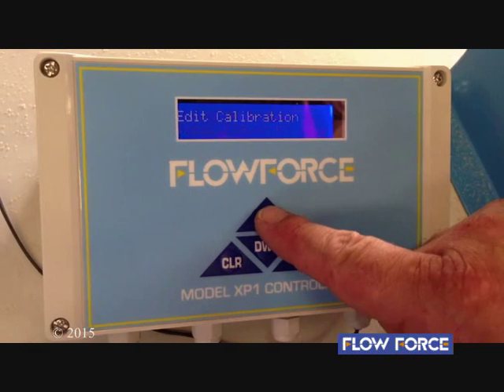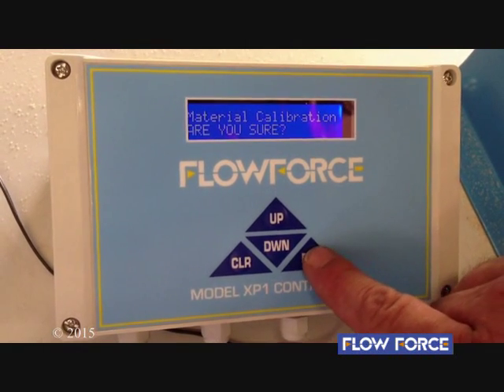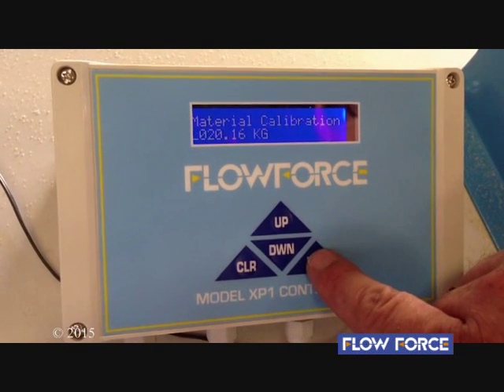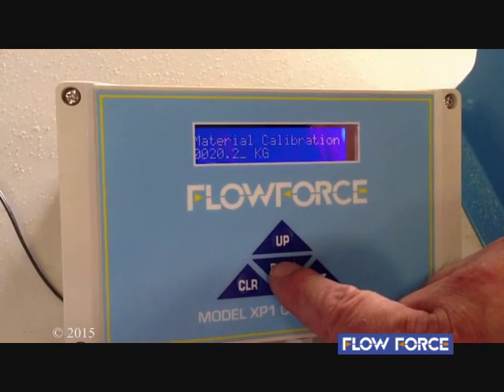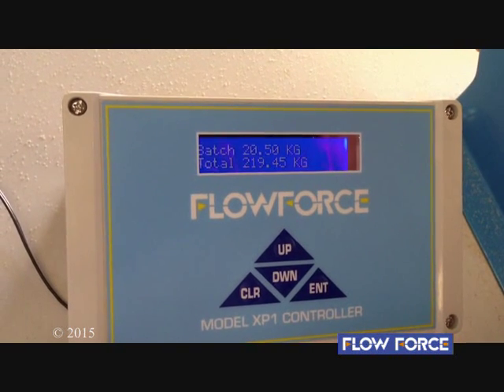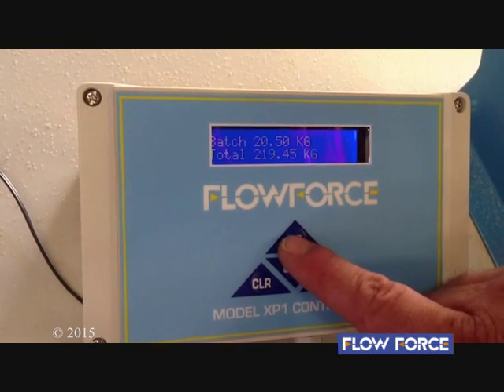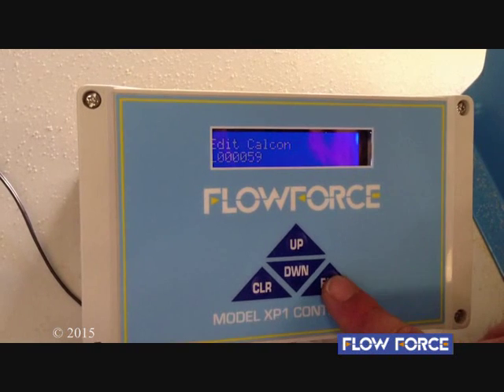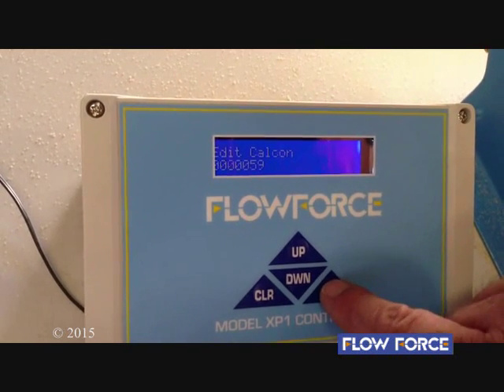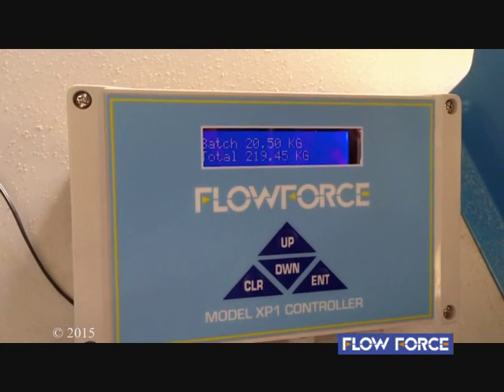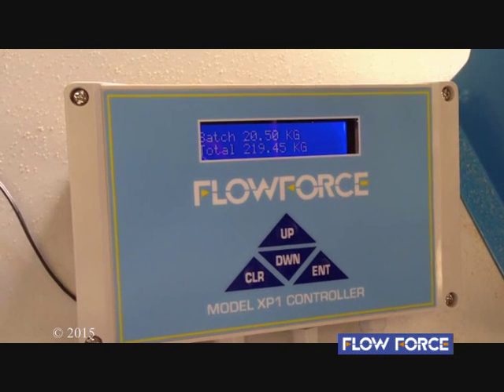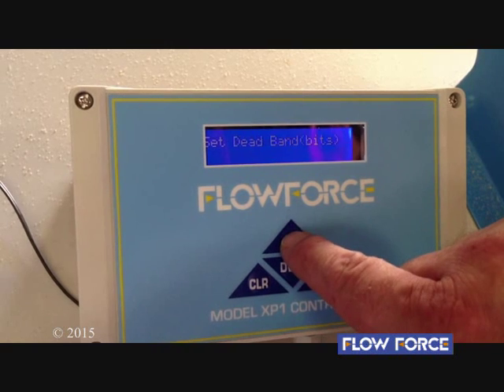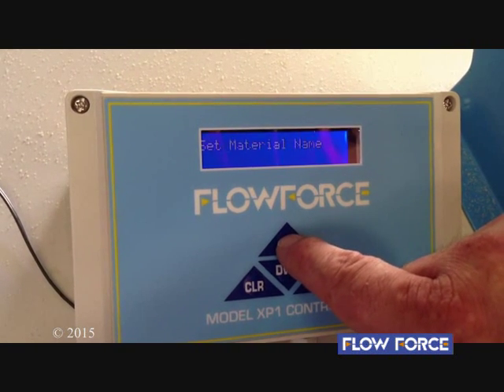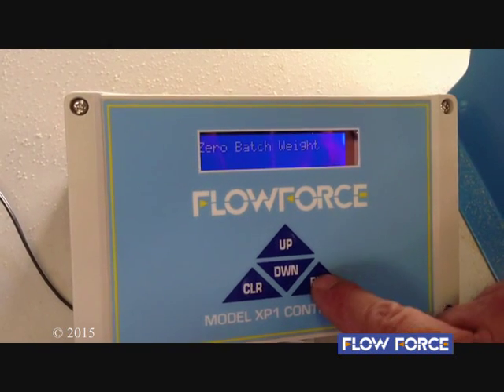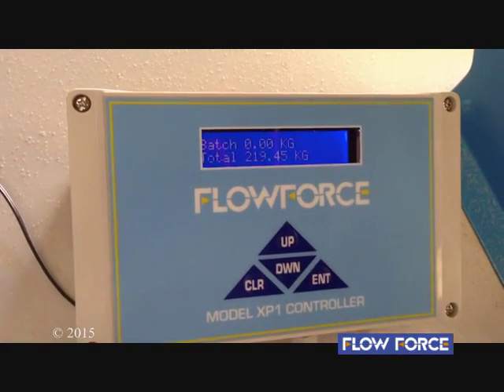So we're back at the XP1 controller. We'll scroll through to material calibration, push enter, and we'll enter the new figure of 20.2. Enter, and while we're here we'll just quickly check what the Calcon is by scrolling through the menu. And the Calcon is now 59. So we'll run one more test now. We'll zero the batch weight while we're here, and ready for test number 3. Batch weight is now zeroed, and we'll get ready to run test number 3.